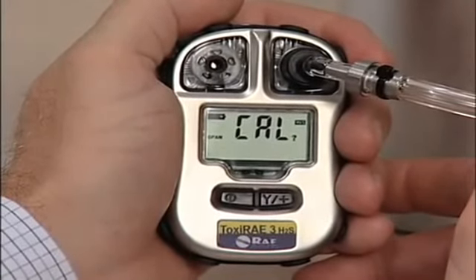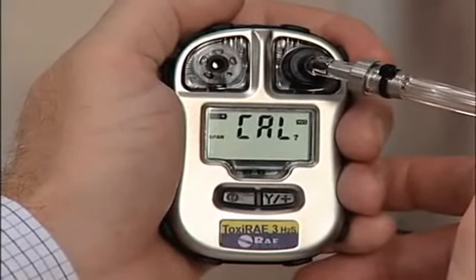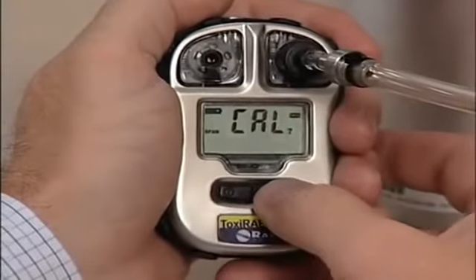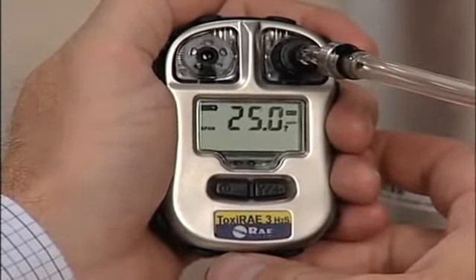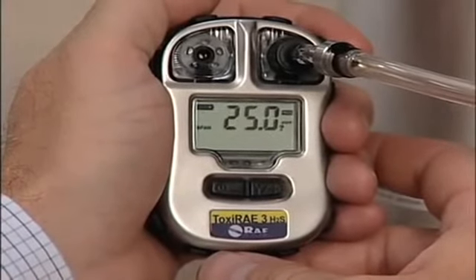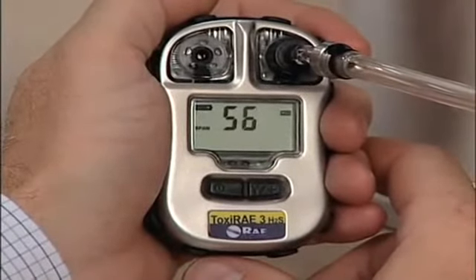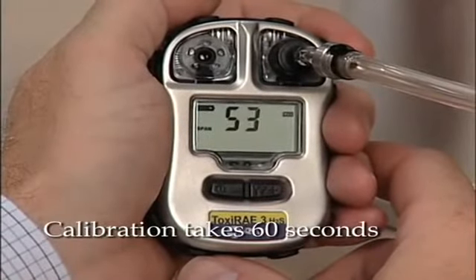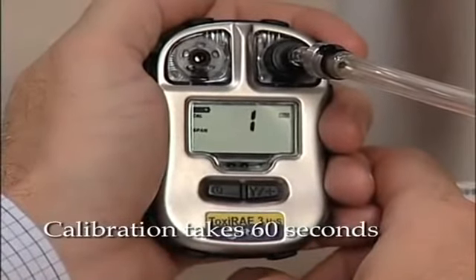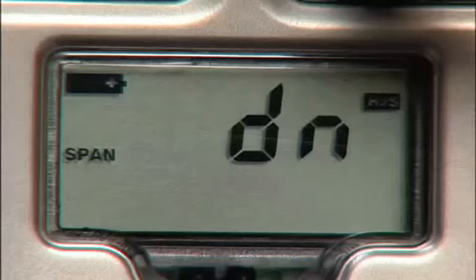Attach the hose from the regulator and the calibration gas cylinder to the calibration adapter's inlet. With the ToxiRAE 3 on in programming mode and with the span CAL menu showing on the screen, press the Y button. A countdown starts and CAL blinks, indicating that the span calibration is taking place. Now start the flow of gas. When the countdown reaches zero, the display alternates between the concentration in PPM and the letters DN for done.